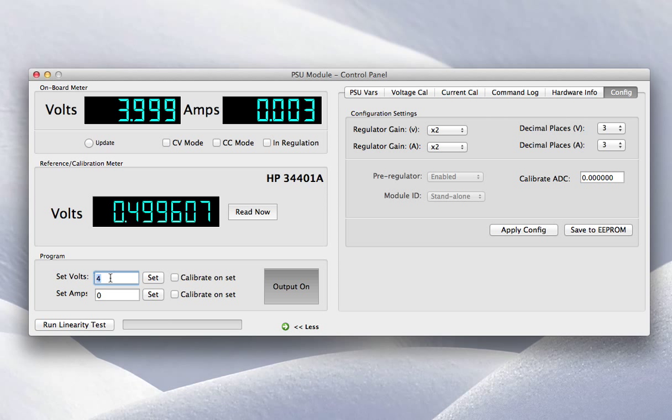So if we come back to the setting for 1 volt, I've got 5 or 6 millivolt difference. If I turn on the calibration, I'll show you that in a second working, but if I turn on the calibration now and do the same thing, it takes slightly longer, but it brings me much closer.